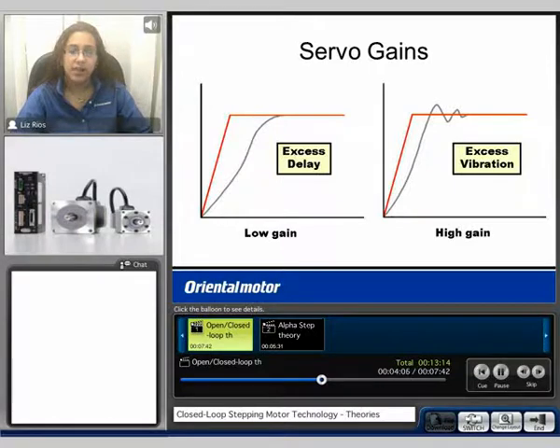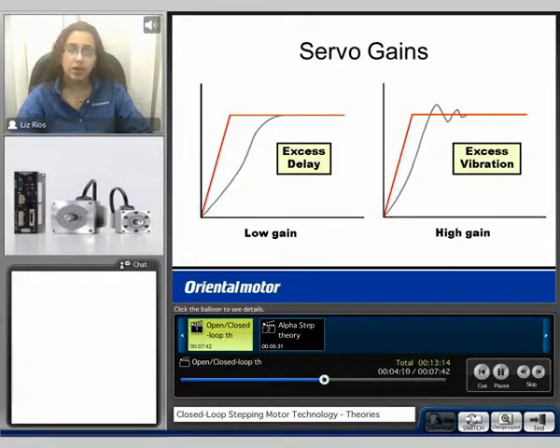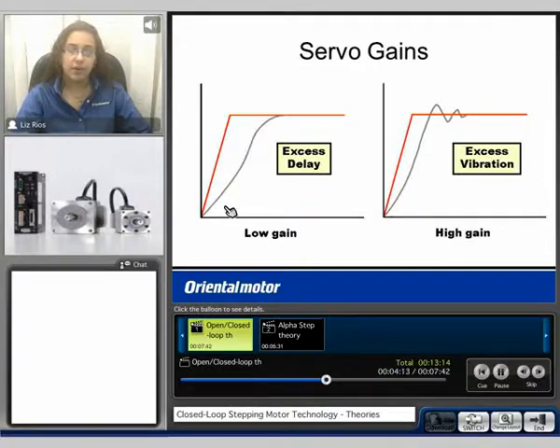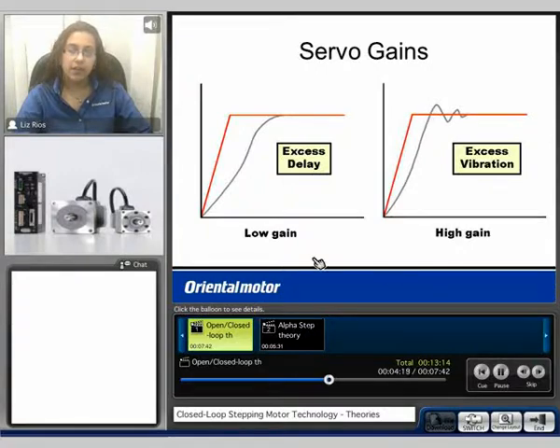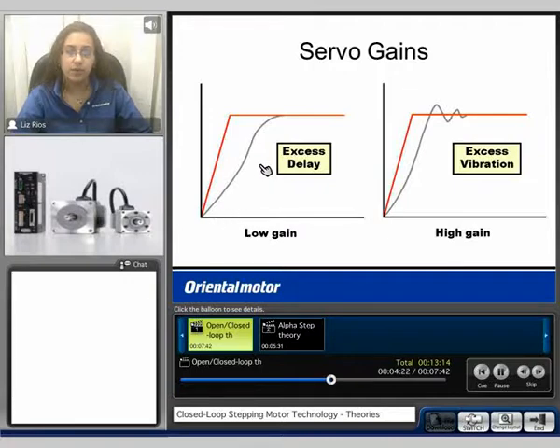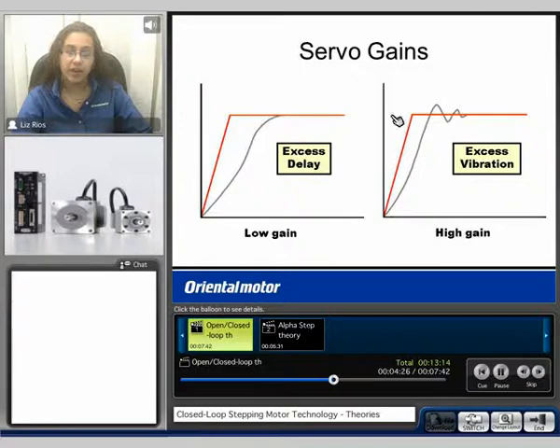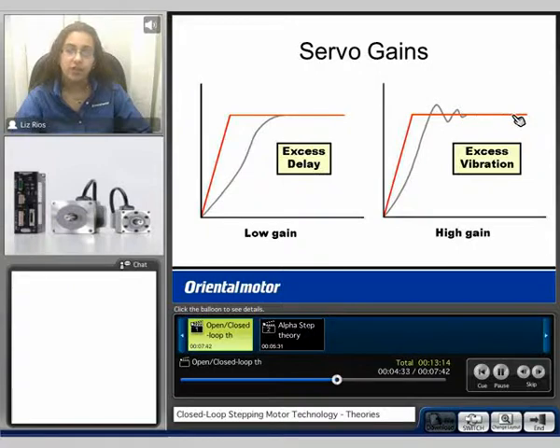The response of the servo is based on your gain settings. Here we can see the same motion profile example, represented here by the red line. Comparing a low gain setting, we can see we've added some delay to our motion profile. If we take that same motion profile and have a high gain setting, now we see that the motor has to overshoot and undershoot to accomplish this motion. Therefore, we've added some vibration to the system.